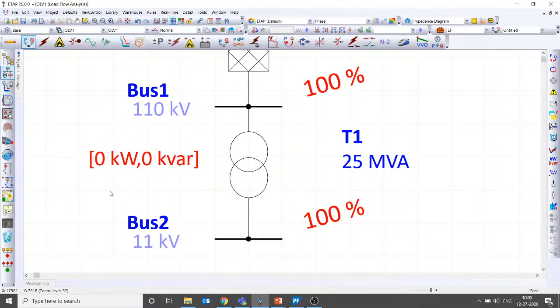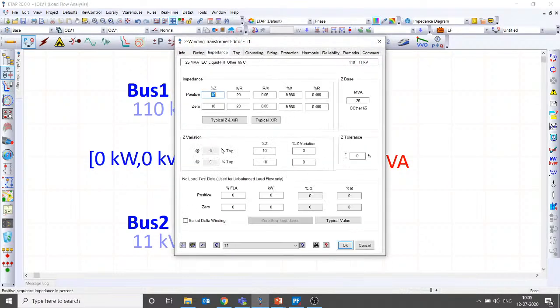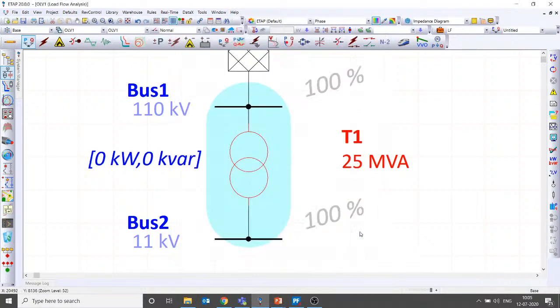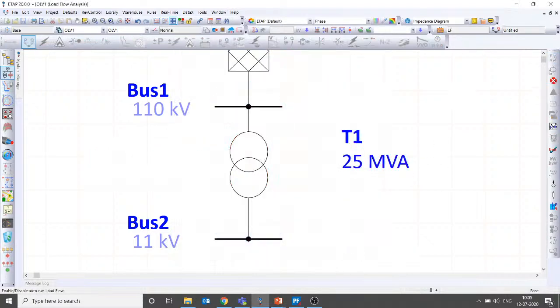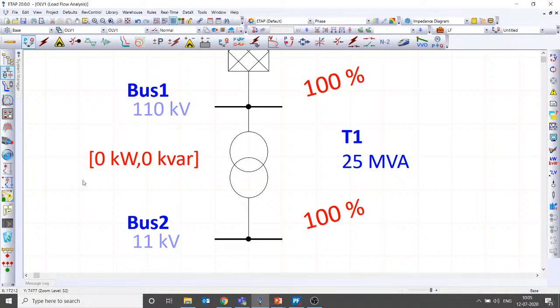Perfect. So even if I give the no load loss parameters, say I am giving the no load current as 0.5% of the full load current, and the loss for this 25 MVA transformer, for example, 10 kilowatt, just for information. Let's look at whether this is captured here. The answer is again, the loss is 0 kilowatt.